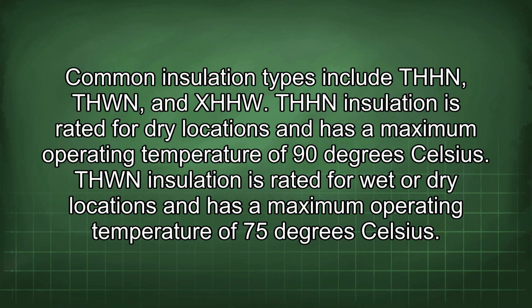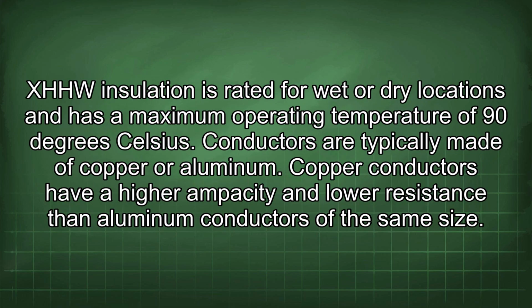Common insulation types include THHN, THWN, and XHHW. THHN insulation is rated for dry locations and has a maximum operating temperature of 90 degrees Celsius. THWN insulation is rated for wet or dry locations and has a maximum operating temperature of 75 degrees Celsius. XHHW insulation is rated for wet or dry locations and has a maximum operating temperature of 90 degrees Celsius.